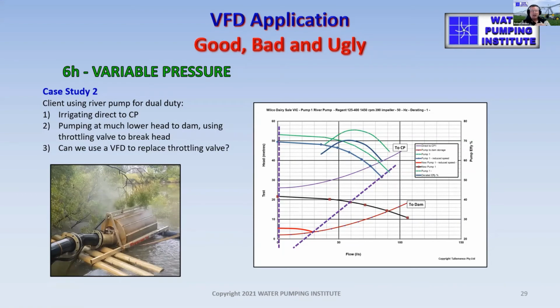So in this particular case, the VFD just doesn't work for the farmer. Yes, it will work, but he'll only get a third of the flow rate out, and therefore he won't have the potential to gather the amount of water that he needs from the river when the river is running high. That's a particularly ugly situation. If you wanted to apply a VFD, you just wouldn't do it. The ultimate solution is a separate pump with a lower head. That's really the only solution.